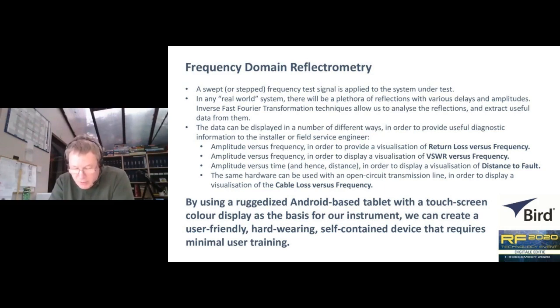Displaying the sum of all the amplitudes on the y-axis and the range of frequencies on the x-axis shows us either return loss versus frequency or VSWR versus frequency. Displaying the amplitude on the y-axis and the time delay on the x-axis could show us the distance to any faults that may be present on the system.